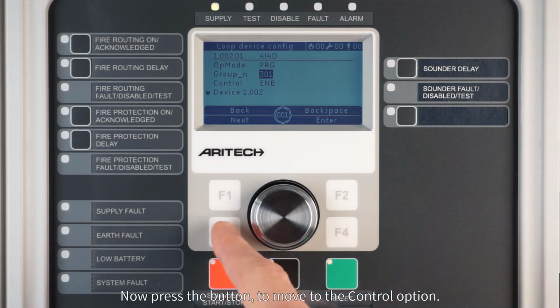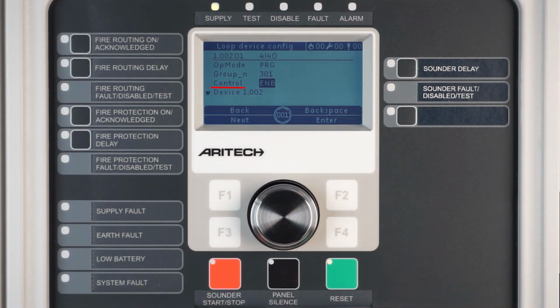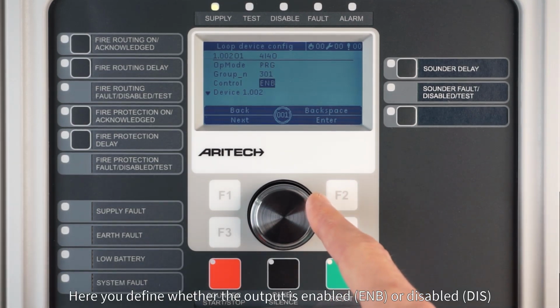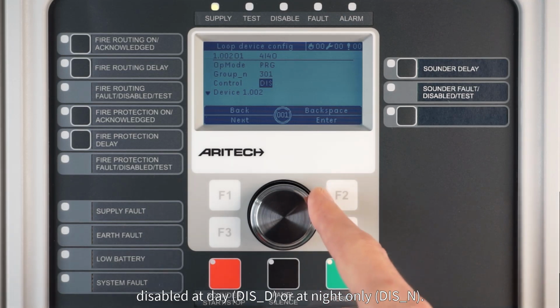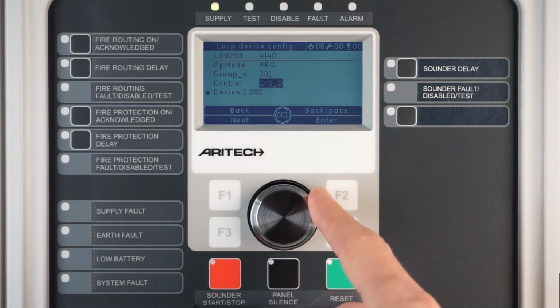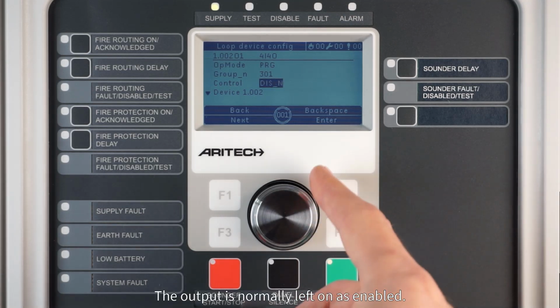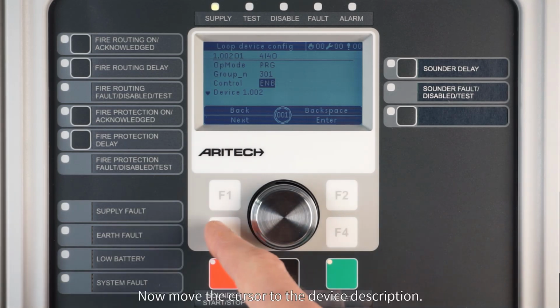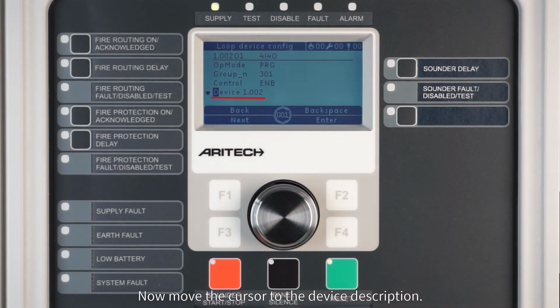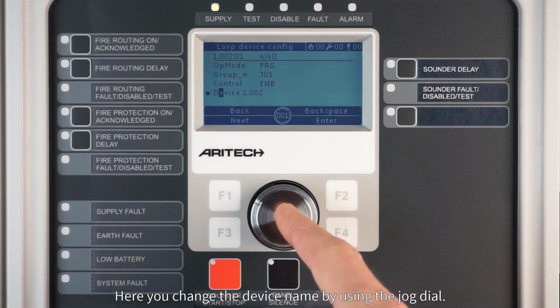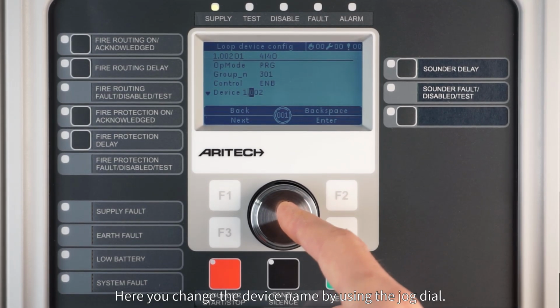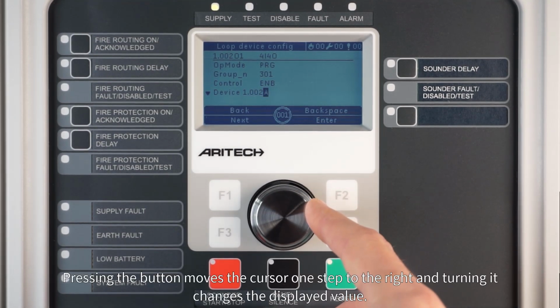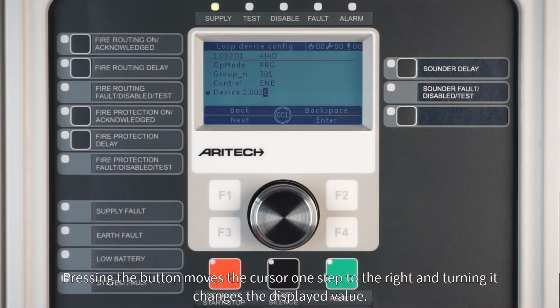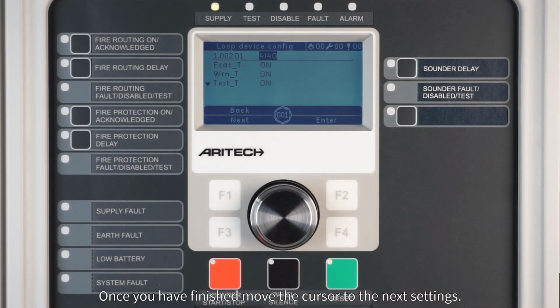Now press the button to move to the control option. Here you define whether the output is enabled or disabled at day, or at night only. The output is normally left on, as enabled. Now move the cursor to the device description. Here you change the device name, by using the jog dial. Pressing the button moves the cursor one step to the right and turning it changes the displayed value. Once you have finished, move the cursor to the next settings.